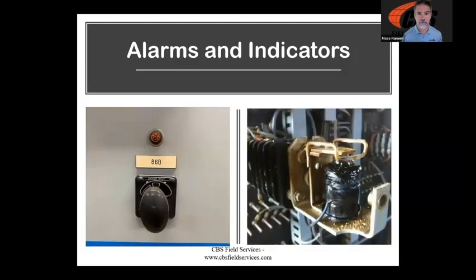This is a great example of another control light failure. I actually took this picture in the field the other week, and it really brought back not a great story, but kind of a horrible story that a client had one time. They had an entire 13 kV switchgear line basically burned to the ground. I mean, hundreds of thousands of dollars in damage, maybe millions of dollars in lost production. I don't know, but all because an individual that didn't have the proper experience, wasn't a qualified worker, damaged the 86 relay coil. And you can see that damaged coil right here.